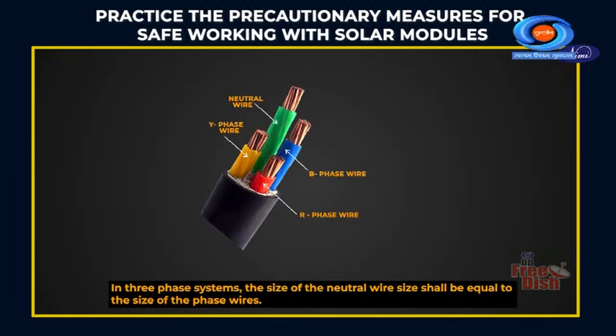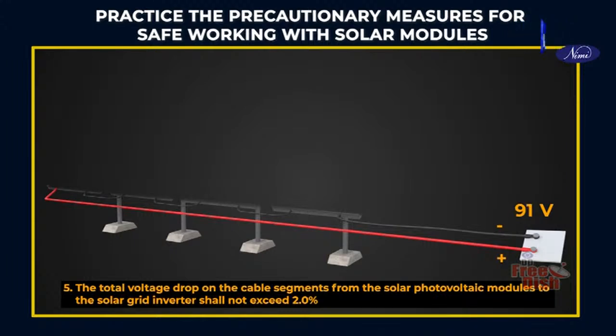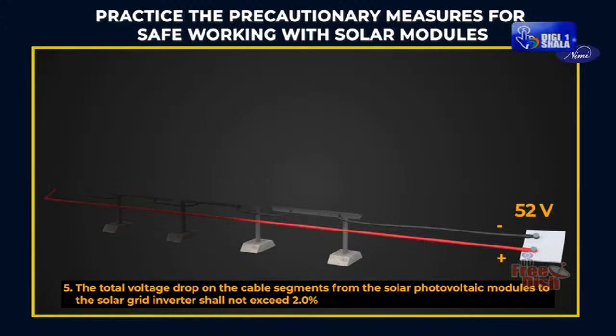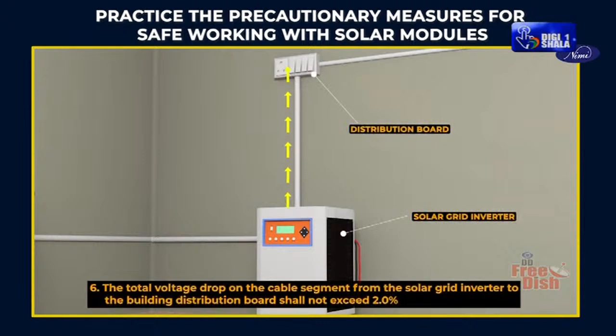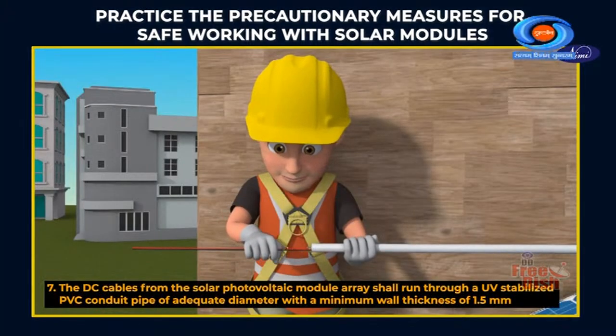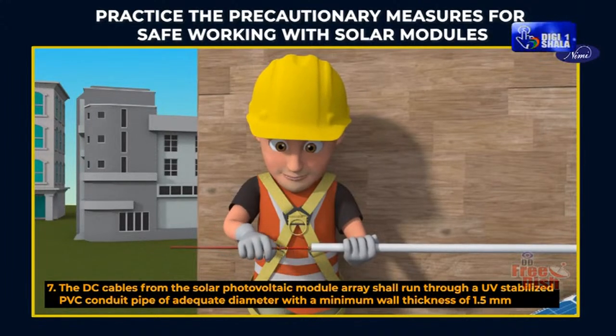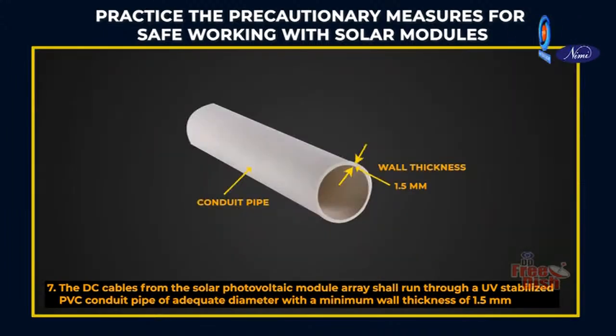In three-phase systems, the size of the neutral wire shall be equal to the size of the phase wires. The total voltage drop on the cable segments from the solar photovoltaic modules to the solar grid inverter shall not exceed 2.0%. The total voltage drop on the cable segment from the solar grid inverter to the building distribution board shall not exceed 2.0%. The DC cables from the solar photovoltaic module array shall run through a UV stabilized PVC conduit pipe of adequate diameter with a minimum wall thickness of 1.5 mm.